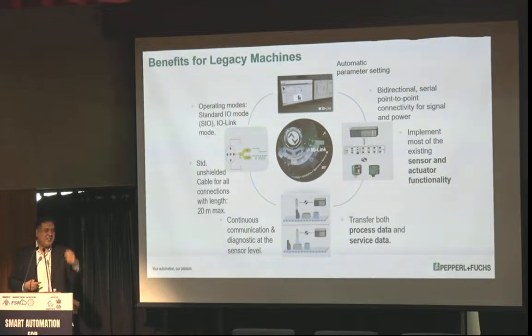Now, if the sensor is able to generate an alarm to tell the operator that there is a position shift and I have to retune it, that will be a helpful event to predict the downtime or reduce the downtime. So this technology, which is IO-Link, which is inbuilt into the sensors, allows you to do all this. If there is a position shift of the sensor, immediately an alarm is raised, and based on that alarm, you can do preventive maintenance easily and quickly.